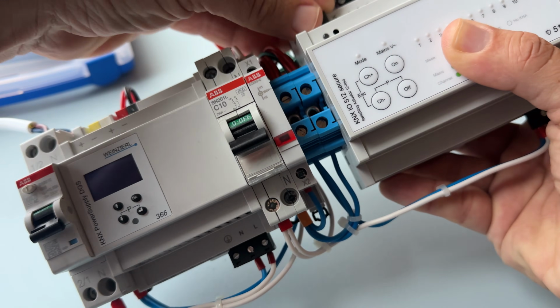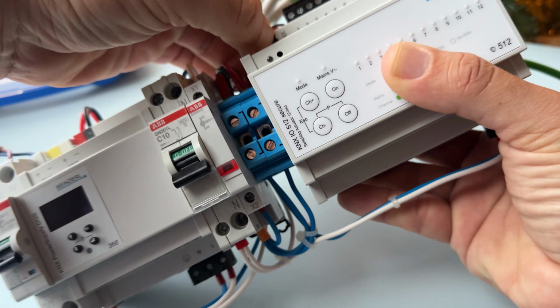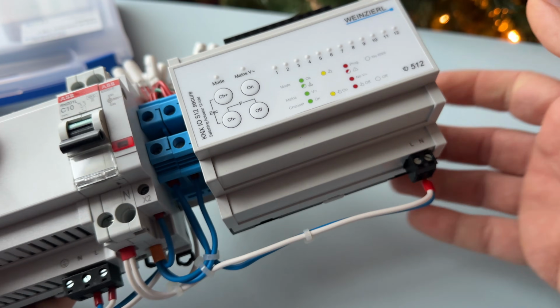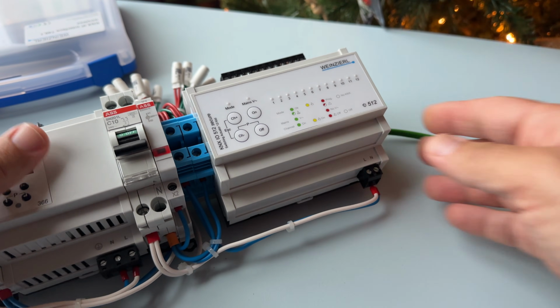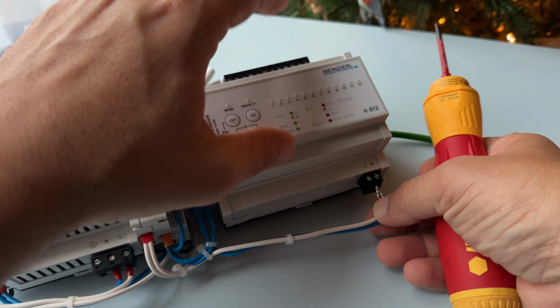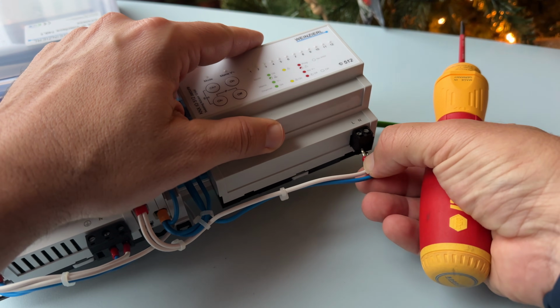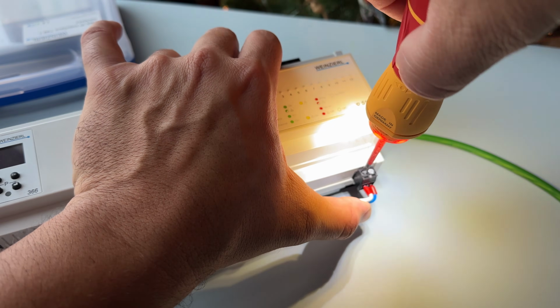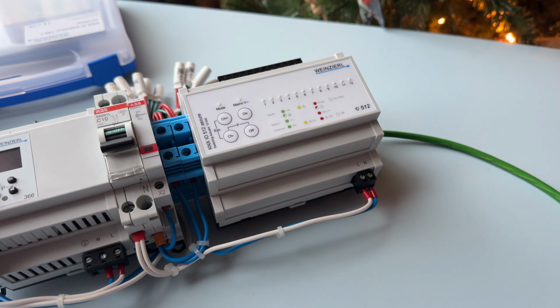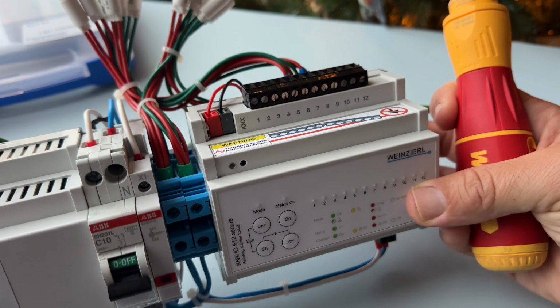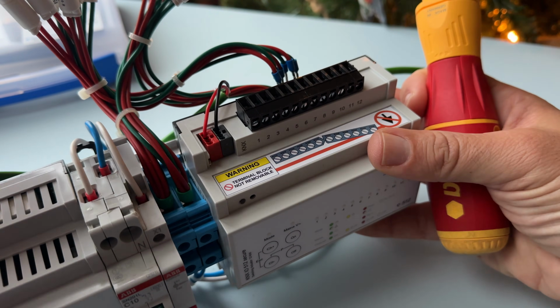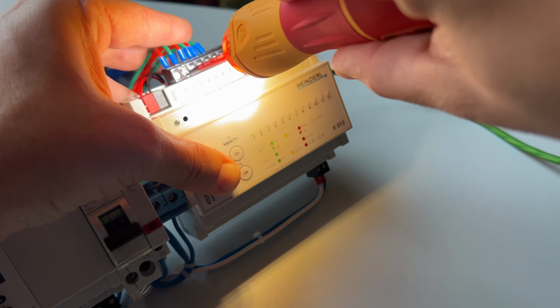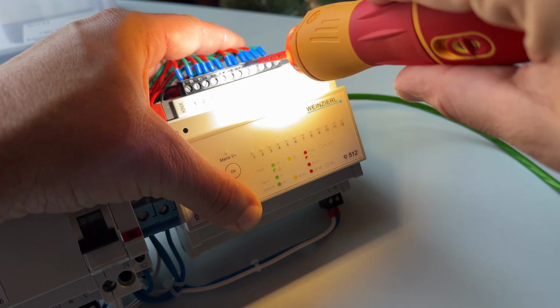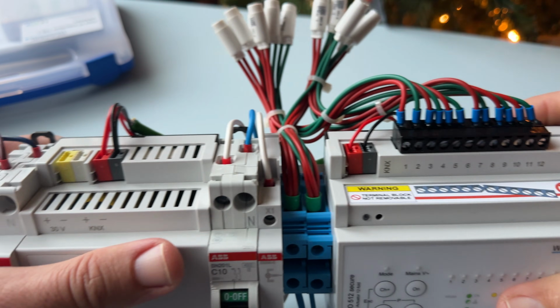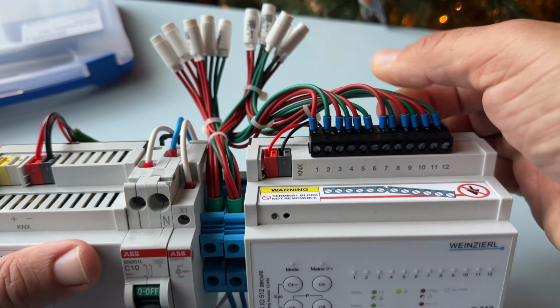Then I'll connect the KNX bus, which is already connected to the KNX power supply. Next, I'll connect the line and neutral to the bottom terminals. And finally, the 12 red and green LEDs that I want to control. Everything is in place. So, let's power it up.